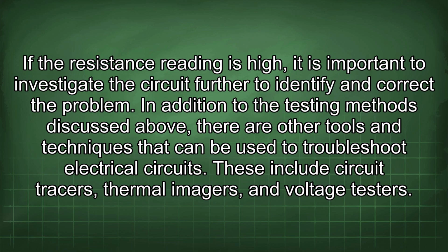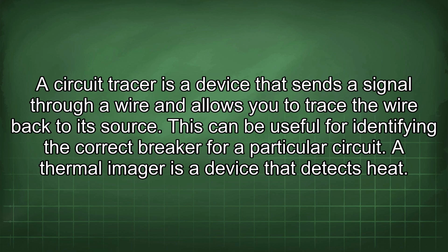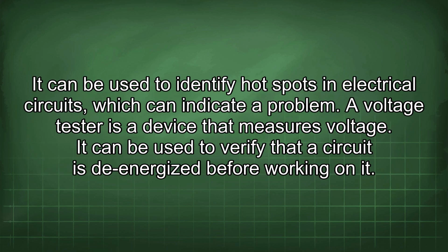In addition to the testing methods discussed above, there are other tools and techniques that can be used to troubleshoot electrical circuits. These include circuit tracers, thermal imagers, and voltage testers. A circuit tracer is a device that sends a signal through a wire and allows you to trace the wire back to its source. This can be useful for identifying the correct breaker for a particular circuit. A thermal imager is a device that detects heat. It can be used to identify hot spots in electrical circuits, which can indicate a problem. A voltage tester is a device that measures voltage. It can be used to verify that a circuit is de-energized before working on it.